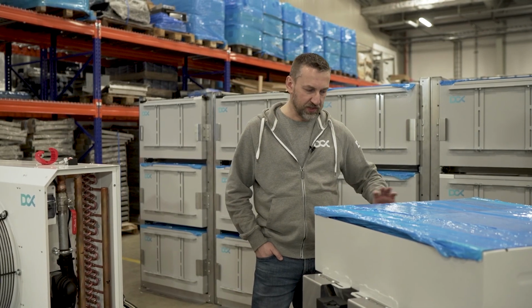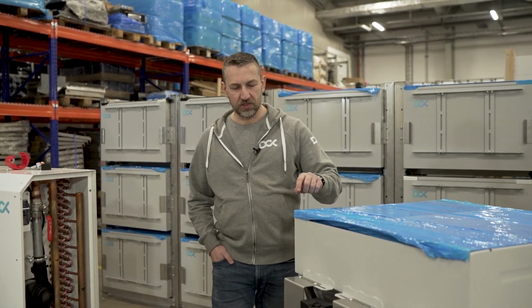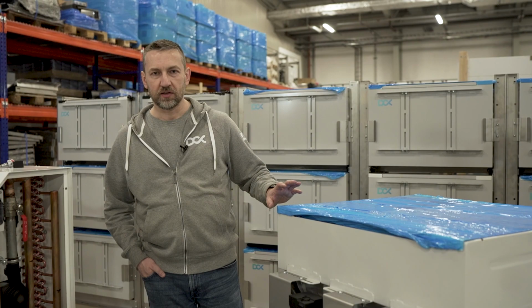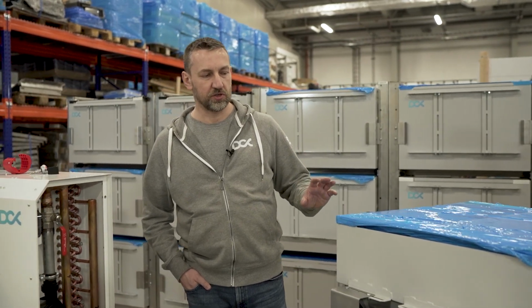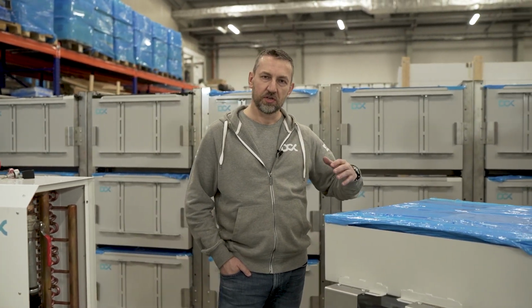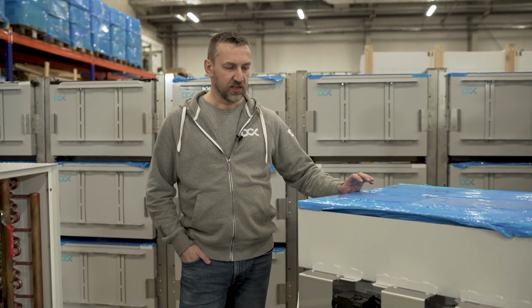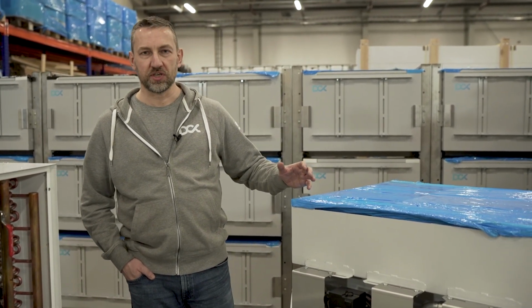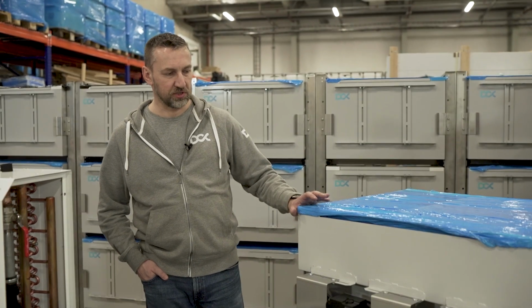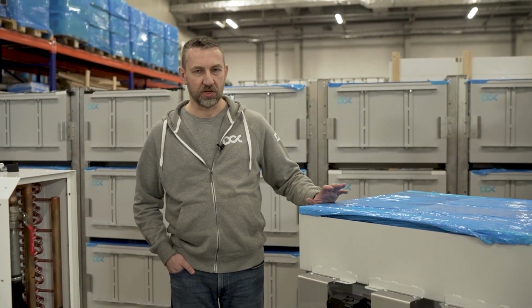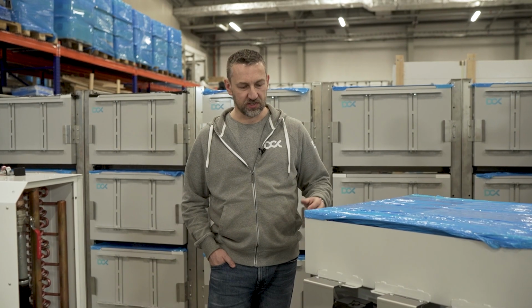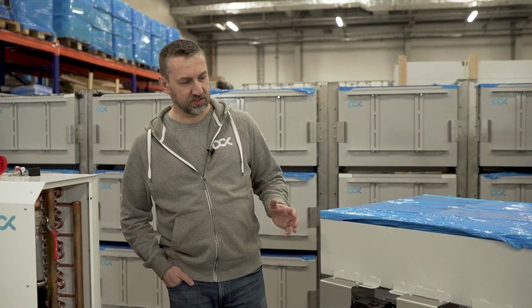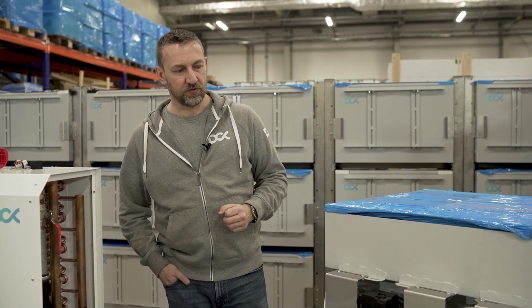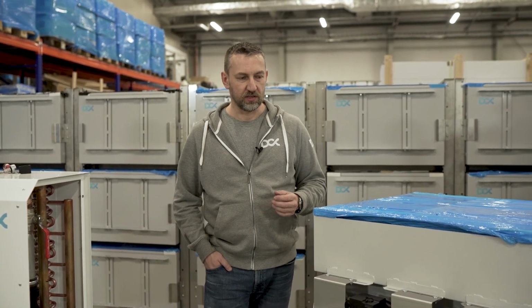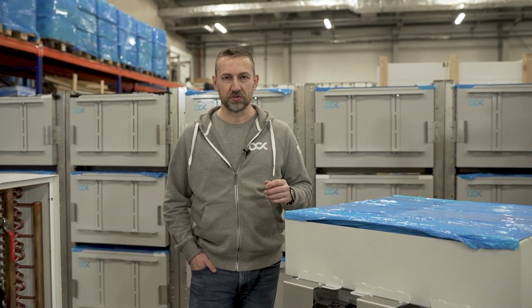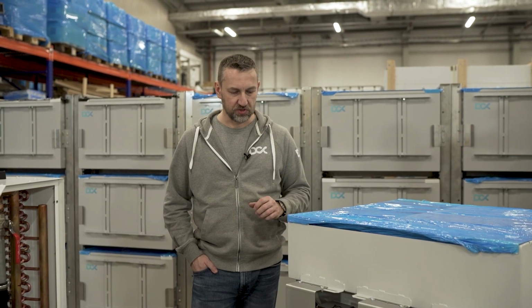We stayed with the metal enclosure because we degrade the level of any humidity, so we can install that in really, really hot, humid areas, because the hot enclosure degrades the humidity significantly. And actually we can reuse the heat. So all the opportunities related to heat reuse, this is what we can provide. The plastic enclosures will never do that. And it must also be properly built to be able to fit 200 kilograms of the immersion hardware, right? So that's why we're using steel enclosures.